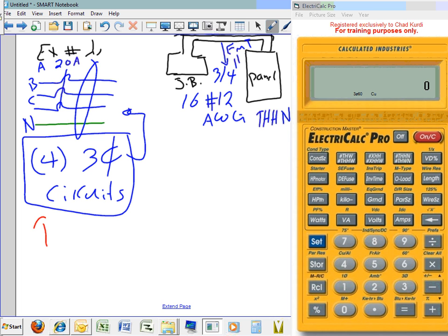Okay, so the first thing you need to do is number 1, find the load. How much current can I pull out of each circuit under these circumstances? Would that be a good idea? Okay, so the first thing we need to know, this is 3-phase commercial, so the load is considered continuous load. Let's say they're feeding lights, the lights are considered continuous load. If you have a continuous load, how much amp you can pull out of a circuit breaker? What's the percentage?